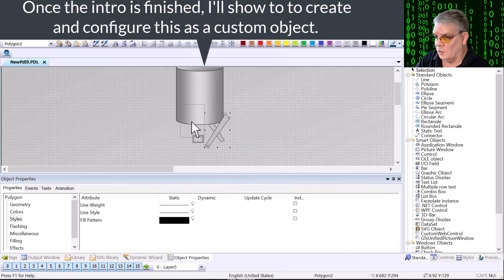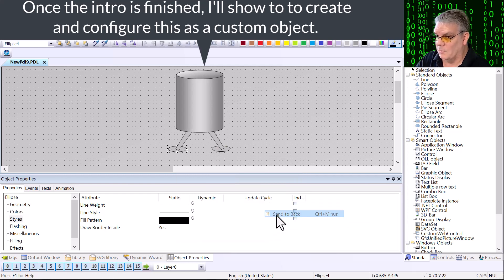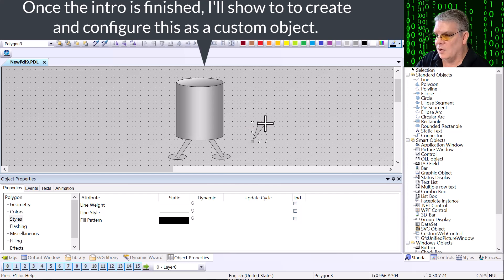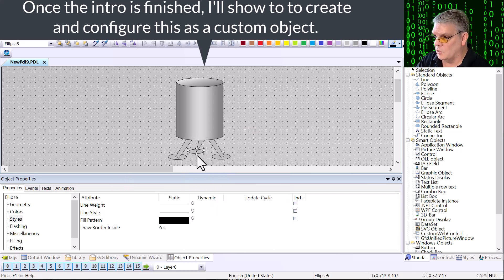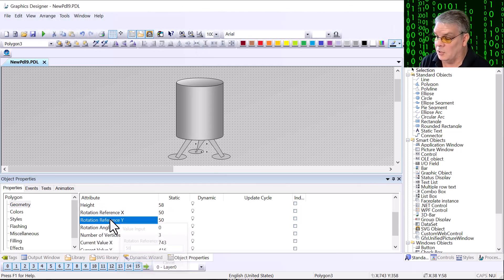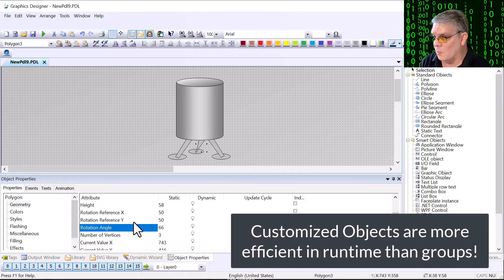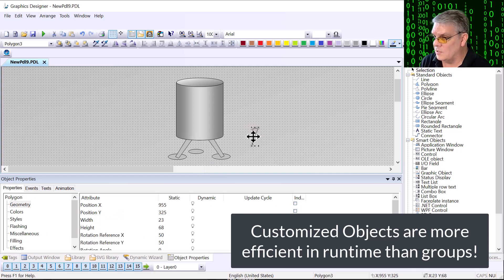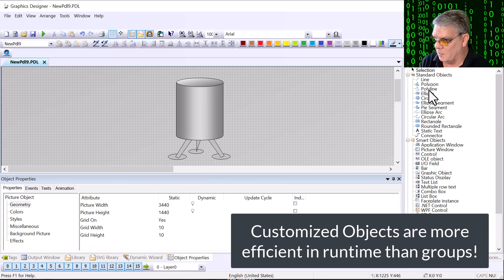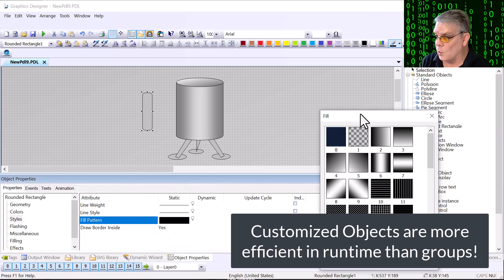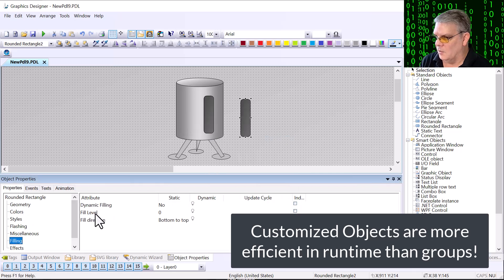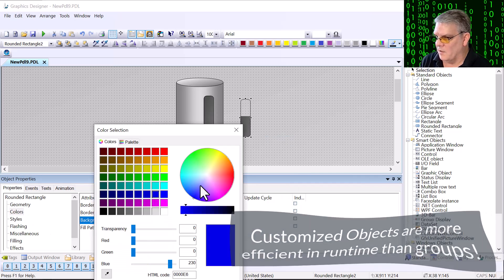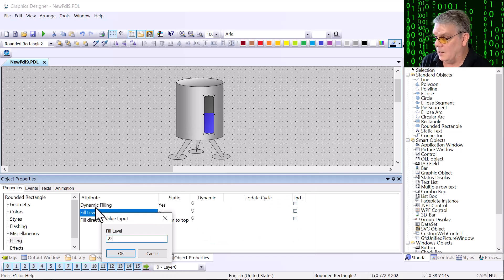You're probably familiar with grouping objects. Groups are just collections of objects that are lassoed and grouped together so you can move them around more easily. However, customized objects are much more efficient and user-friendly than groups. Customized objects are more efficient in runtime because they lose the overhead of the individual components and are seen as one object by the runtime graphics engine. When groups are loaded into Graphics Designer they are treated as a bunch of objects and will take longer to load and to animate.